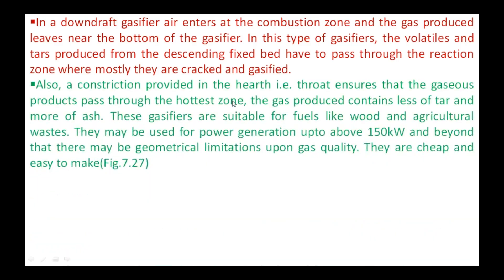A constriction is provided in the hearth where combustion takes place; this constriction is called the throat, and it ensures that gaseous products pass through the hottest zone. The producer gas contains less tar and more ash, because the tar is cracked — some of it forms ash and the remaining forms gas. That is why the producer gas has an ash content.